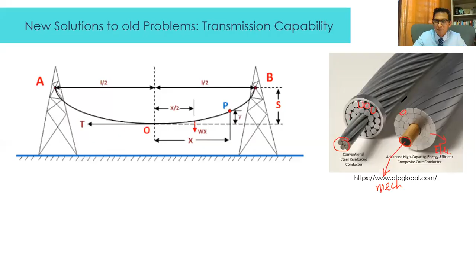They've also replaced the steel reinforcement with carbon fiber. This gives you the mechanical strength, and the aluminum provides the electrical properties. Ultimately, you have a new conductor, most likely the same size, which is able to carry much more electricity.